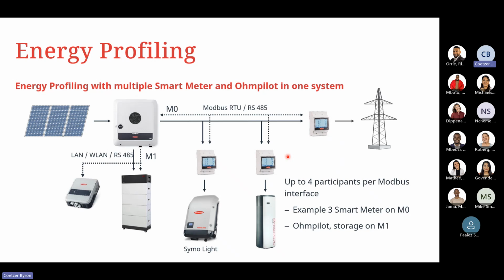So next is just on energy profiling. This is if a client has multiple meters that they want to use for different features and functions. If we have a specific load that we want to measure, for example, a geyser or a separate inverter in the system, we can have up to 4 meters in total. So you'll have one master meter and 3 separate consumption meters individually in the system itself.